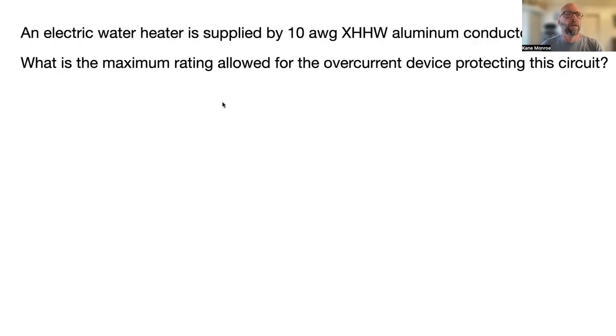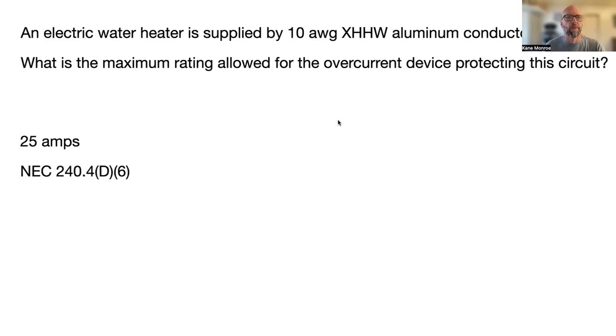Next question: an electric water heater is supplied by 10 AWG XHHW aluminum conductors — what is the maximum rating allowed for the overcurrent device protecting this circuit? Don't get caught up with all the extra information. The answer is 25 amps, found at NEC 240.4(D)(6). Make sure you highlight 240.4(D)(6) — 25 amps.